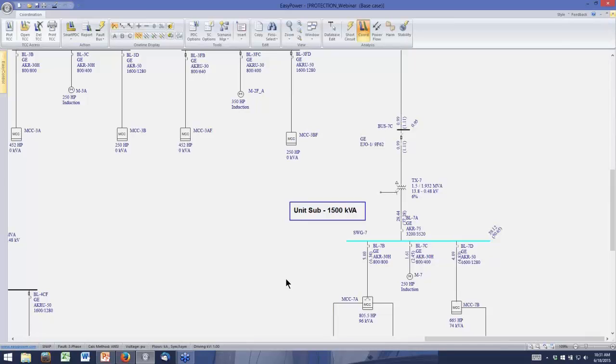So typically when we do look at our coordination and draw the TCCs, our circuit breaker, molded case breakers, and low voltage power circuit breakers, we're generally always looking at fuses. Mostly we're looking at phase overcurrents. So when we start talking about ground faults, then we have to make sure we define those settings in the program so we can display those TCCs if we want to look at them. So we'll take a look at how we do that and go back to database real quick here.